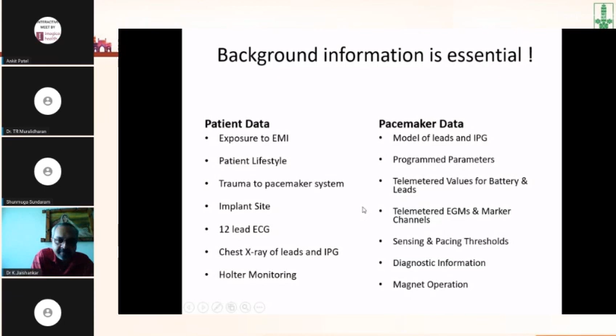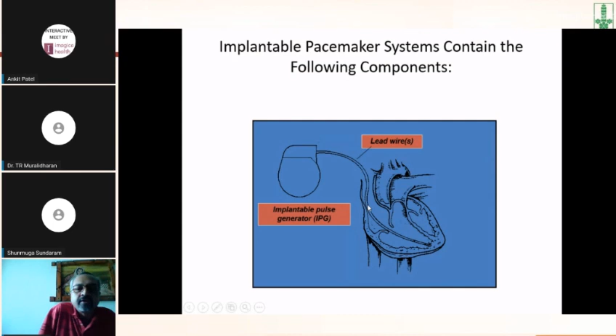So this has been told clearly. What's important to bear in mind is that we seldom see problems with the dual chamber pacing system. All the pacemaker malfunction, or so-called pseudo malfunction, occur primarily with the single chamber based pacing system. The pacemaker system consists of the implantable pulse generator, called IPG, with a wire connected on one end to the pulse generator and the other end fixed either with a tined lead or with a screw-in lead onto the myocardium. Next, please.